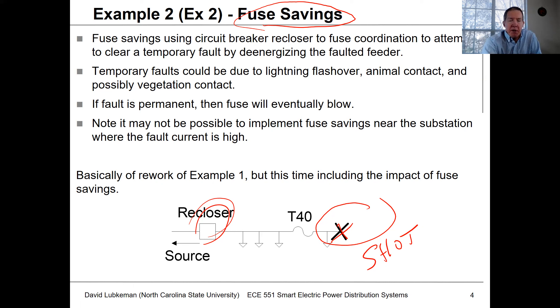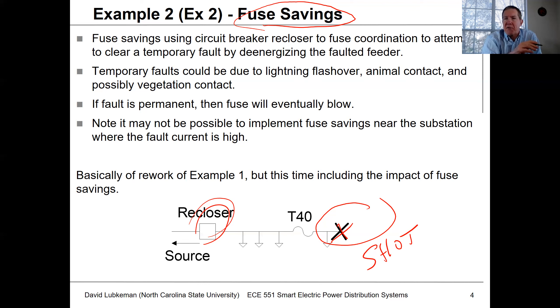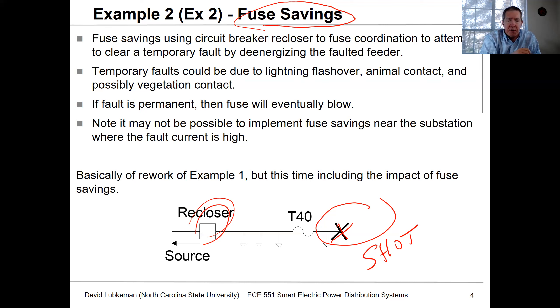It's not always possible to do fuse savings. If we're at the top of the feeder, sometimes the fault current is so high that we can't get the right coordination — the fuse will blow right away anyway. So we don't always have fuse savings done uniformly on a whole distribution feeder; we might pick our spots where we want fuse savings and other spots we may not.